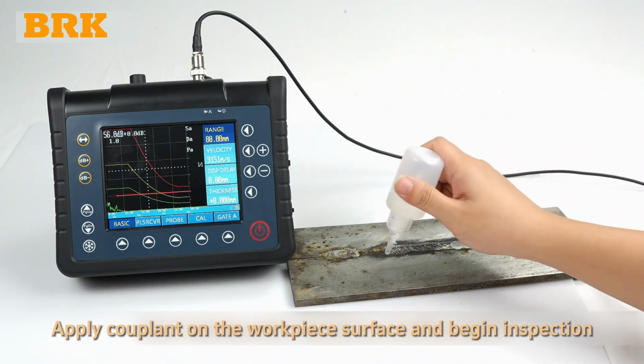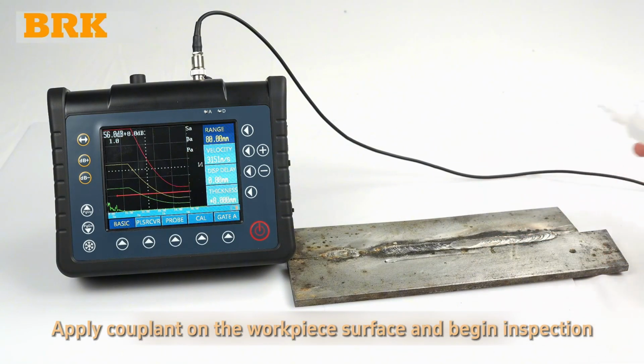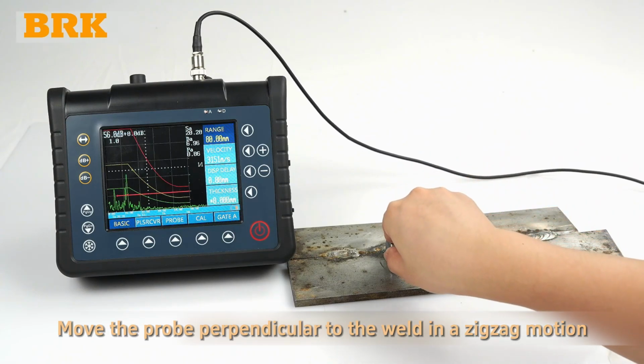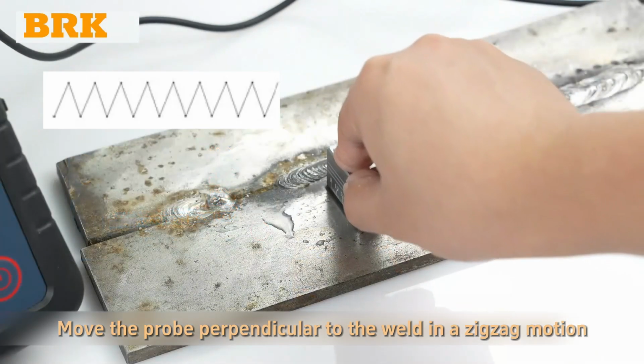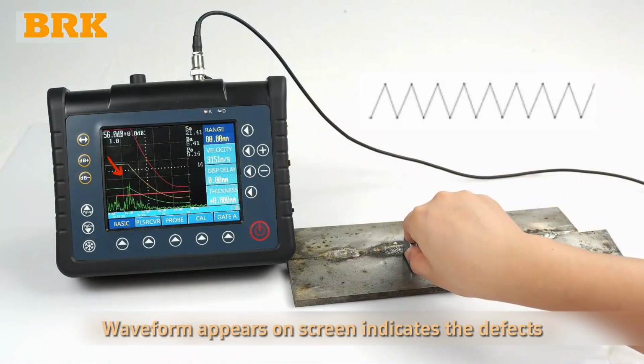Apply couplant on the workpiece surface and begin inspection. Move the probe perpendicular to the weld in a zigzag motion. Waveform appears on screen indicates the defects.